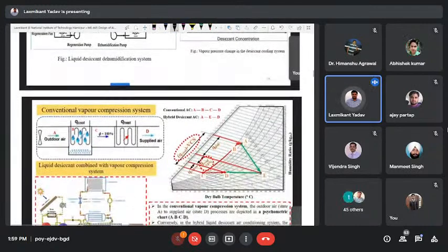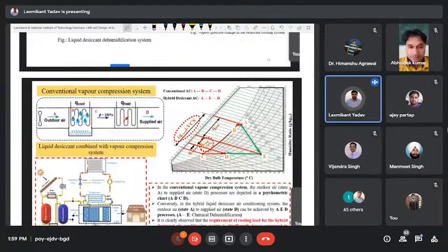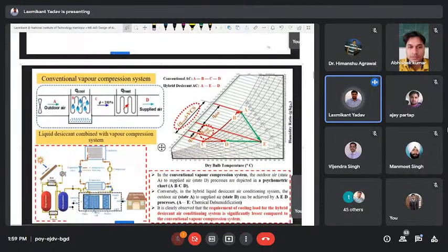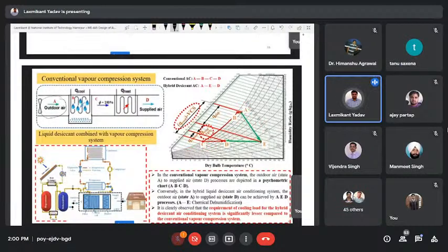Okay, so this graph represents the conventional air conditioning and desiccant air conditioning. You can see this is the conventional vapor compression system. In the conventional vapor system, the air is supplied to the cooling coil, so there will be condensation. The condition of the air is almost saturated, so again reheating is required. So this is an excess wastage of energy. This red line shows A, B, C, D. This red line indicates the conventional cooling representation on the psychrometric chart.